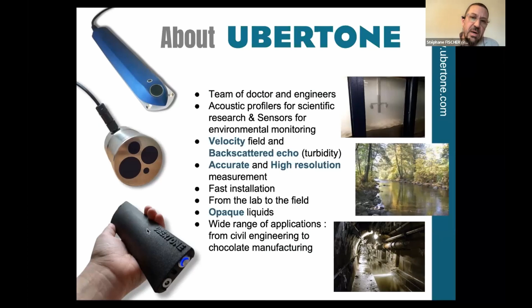speak about turbidity, acoustic turbidity. We do this measurement accurately with a high resolution down to the millimeter with fast installation. We do measurements from the lab to the field. Of course, as it's acoustic measurements, we can measure in opaque liquids, and this is for a wide range of applications, typically from civil engineering up to chocolate manufacturing. So here we have a few examples of our instruments. But now I will just switch from Peter's talk to acoustic turbidity.